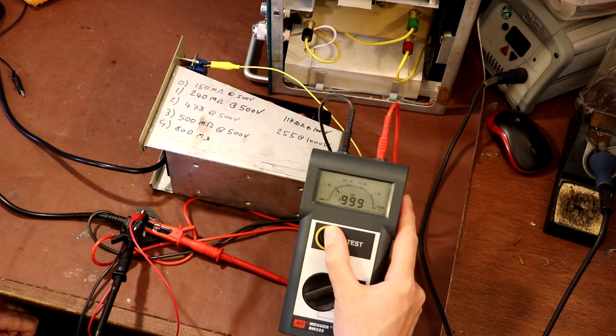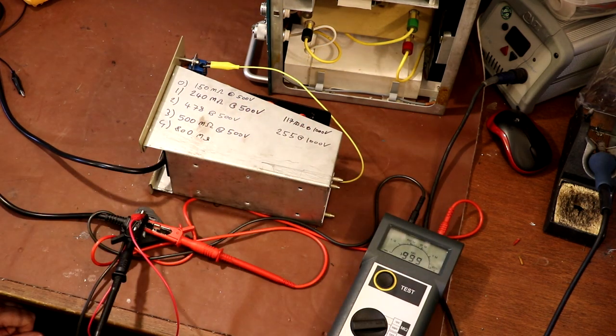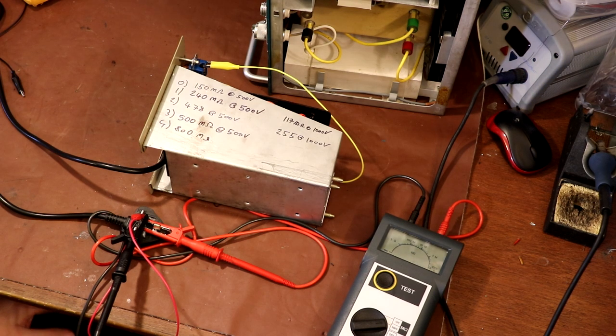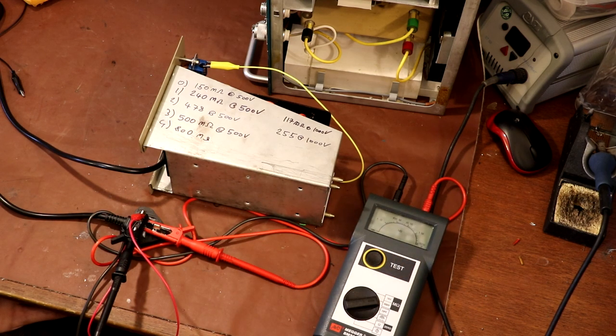of the problems that we had before is that there must have been some dampness in these transformer windings, which doesn't surprise me because where we actually got this from, it was stored in a greenhouse. Literally it was a big greenhouse, and it was cold and it was damp and it was wet. It's definitely absorbed moisture. Now that shouldn't have made my earth leakage trip.